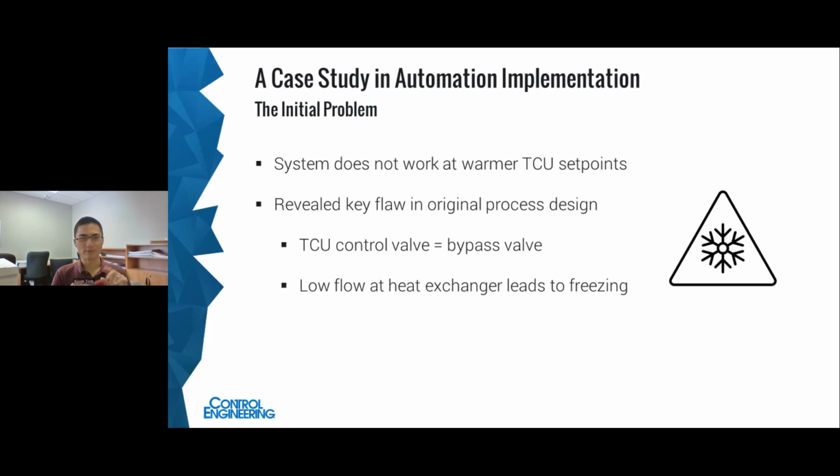So what's the problem here? What we were having was the system only worked for the colder TCU set points around -60, -70 degrees Celsius, but not at the warmer TCU set points around -30 to -40 degrees Celsius.